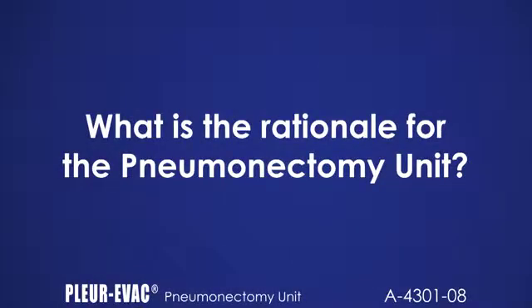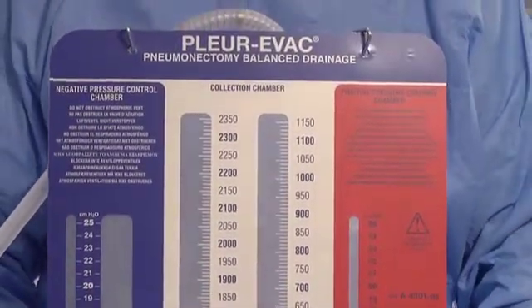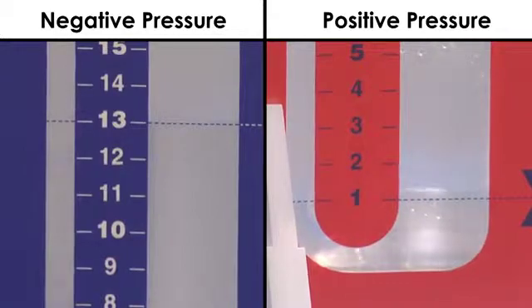What is the rationale for the pneumonectomy unit? The Pleur-Evac Pneumonectomy Unit limits the patient pressure between the levels of where the negative and positive pressure columns are filled with water. The usual fill levels are minus 13 cm in the negative pressure column and 1 cm in the positive pressure column. Therefore, the patient, when attached to the unit, is limited to between minus 13 cm and plus 1 cm of pressure. When either of these two levels is attained by the patient, air enters the appropriate U-tube column chamber, bringing in atmospheric air and limiting the patient pressure to that level. This was designed to limit excessive negative or positive pressure attainment in the affected patient space.